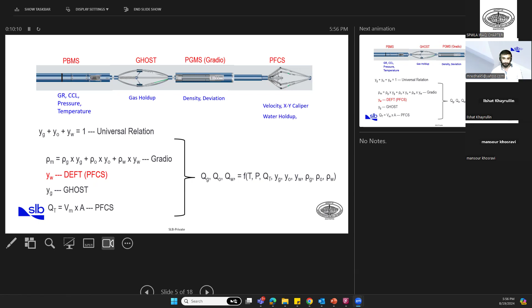So here is the workflow for all the PLTs that we are going to do in order to end up with the rates for the quantitative measurements. In the PFCS, we have the four arms, with four electrical probes on each arm, and in the middle there is the spinner. From this spinner we get the quantitative measurement. Without it, for sure, we cannot, because this one basically measures how much we are producing or injecting, along with other sensors that we combine together to come up with the total rate or the rate for each phase. But does this spinner give us the velocity directly?